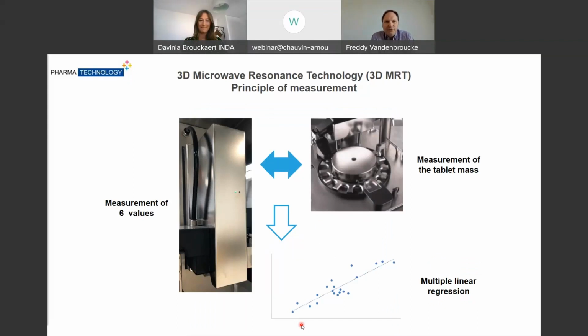The 3D microwave resonance measurements are indirect measurements, so it requires a calibration, and it is a model that will link the measured microwave changes to the real mass of the tablet. For this, during the recipe creation, 20 tablets are sent one by one through the sensor and diverted to the 4-parameter tester. For each measurement, we observe 6 parameters at the microwave sensor, and we get the mass from the weigh cell. The software finally builds the model as a multiple linear regression over those 20 arrays.